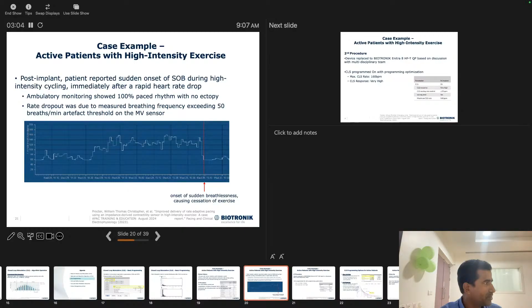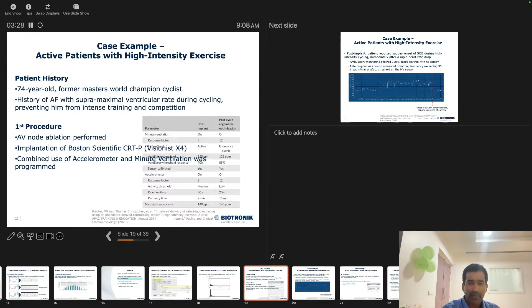The rate drops were due to measured breathing frequencies exceeding 50 breaths per minute artefact threshold on the MV sensors, the minute ventilation sensors, which were also on. The patient was repeatedly complaining that he was not able to do the cycling. These are the parameters programmed in the minute ventilation, also shown here. I didn't go through it much. Minute ventilation on, response factor is 8. These are a few of the parameters programmed in the minute ventilation program.